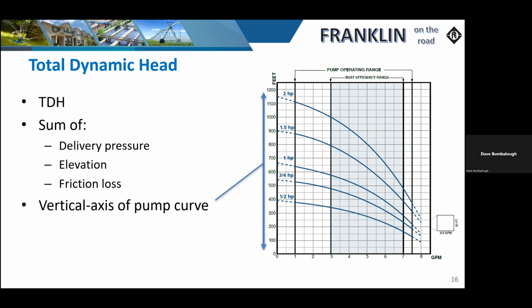So if we were to take a look at a pump curve, and of course, as we're looking at this pump curve, you'll notice this is a 5 gallon per minute pump curve. And as you can see, we're not going to get to 15 gallons per minute off of this. We're only going to achieve 5. So if we do have a shower going, a dishwasher, maybe something else in the kitchen, you're going to grossly overshoot that 5 gallon per minute performance.